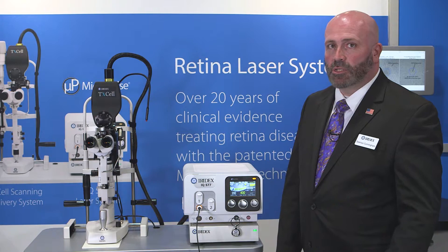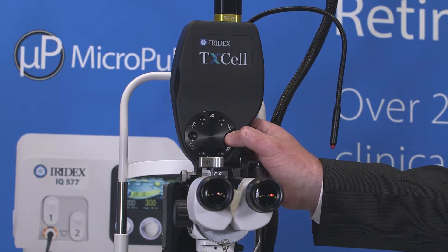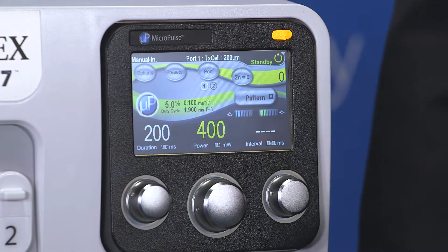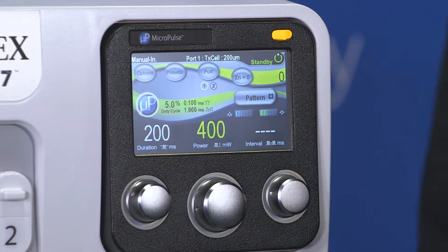The next step would be to select your spot size. The spot size can be selected by rotating the dial on the slit lamp adapter. You can also check the spot size by the black line across the top of the LCD screen — here it says Port 1, TxCell, 200 microns.